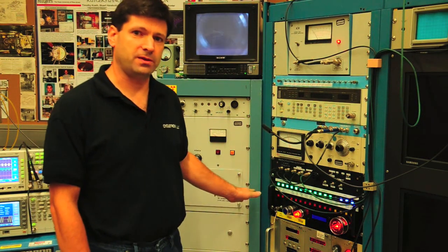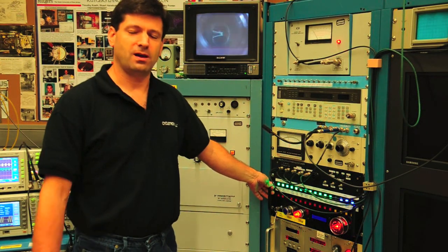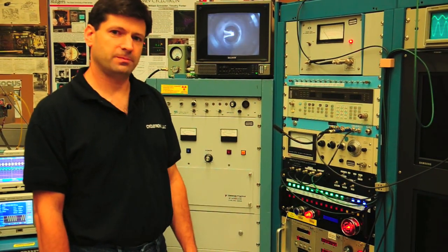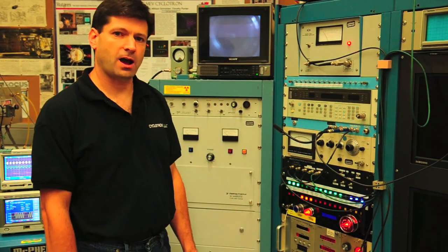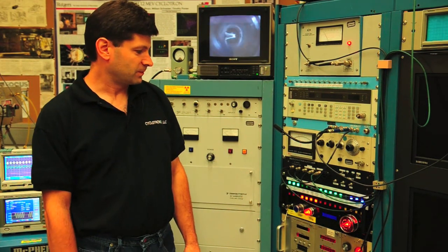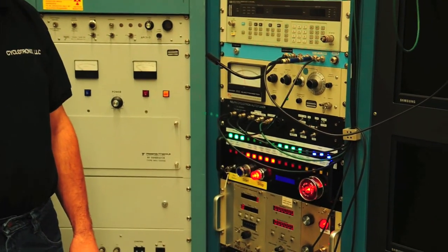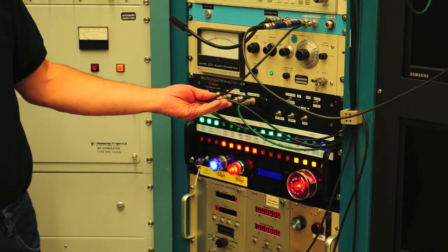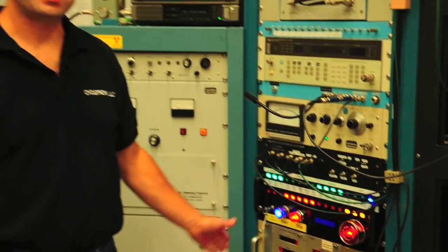Now it's important to keep in mind that this was not designed for human safety. This was designed for limited safety of the equipment and the cyclotron itself. And we're going to stop the water for more than a preset amount of time. You're going to see the water alarms. And then on the right hand side, you're going to start to see the output switched off. Right now everything is still in the on state. We have a little window of time. And we lost our water flow and we shut off various devices. Keeps our cyclotron nice and safe.